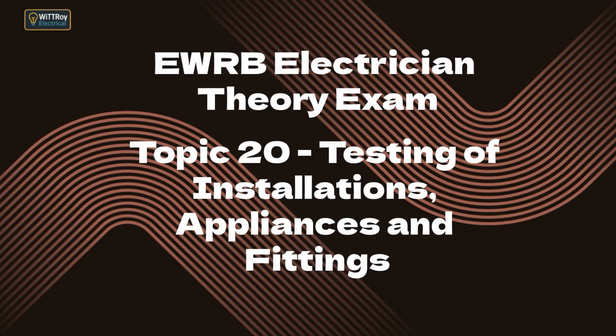Summary. Testing must follow a logical order and be well planned. Visual and mechanical checks are required before instrument testing. AS/NZS 3000 and AS/NZS 3017 specify all mandatory tests. Key tests include continuity, insulation resistance, polarity, ELI, PSC, RCD tests, and operation. Sensitive fittings must be protected from insulation test voltages. Special installations require additional testing under companion standards.